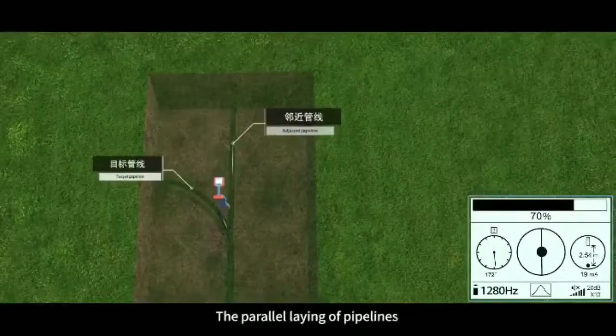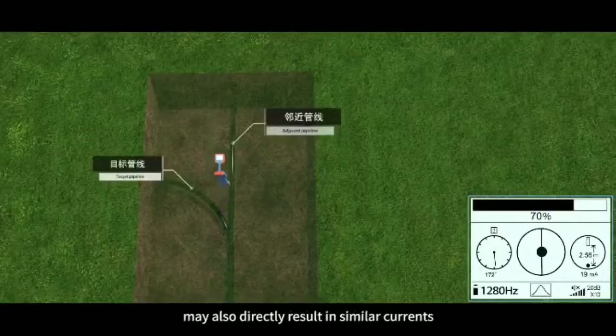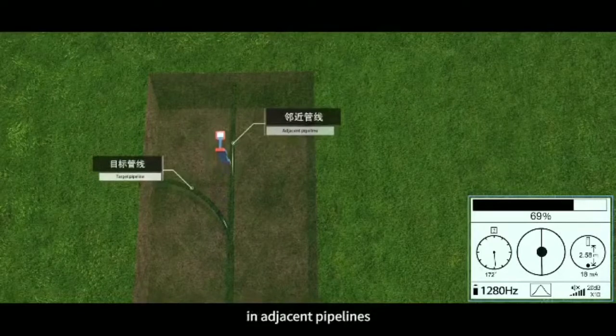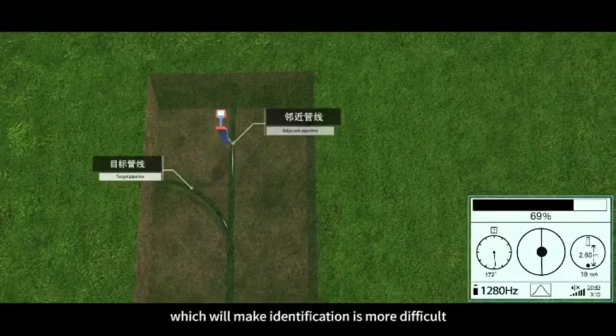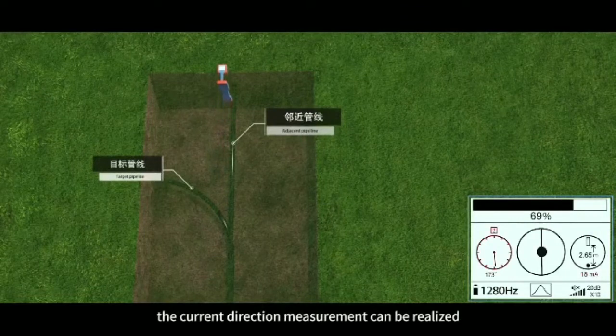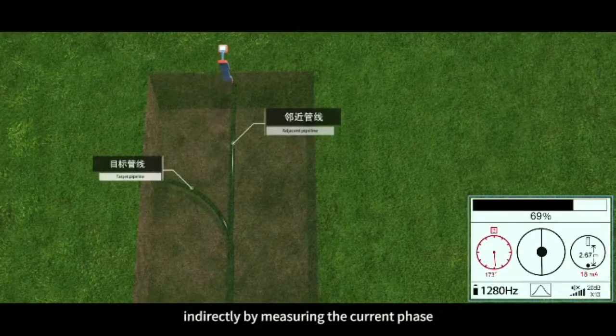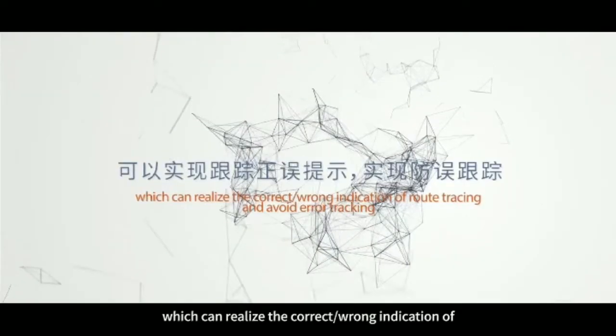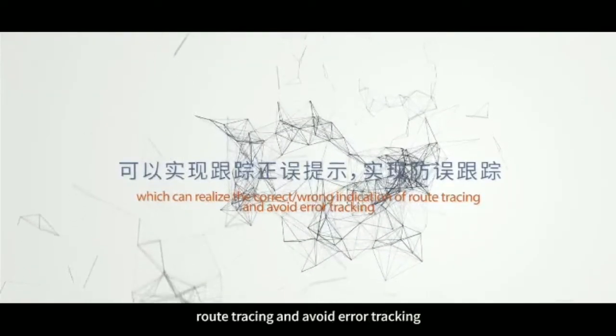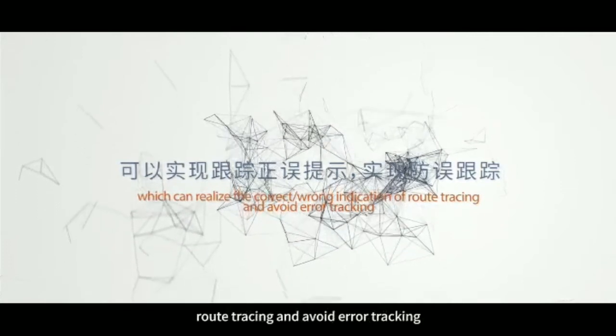The parallel laying of pipelines may also directly result in similar currents in interfering pipelines, which will make identification more difficult. In this case, the current direction measurement can be realized indirectly by measuring the current phase, which can give a correct or wrong indication of route tracing and avoid error tracking.